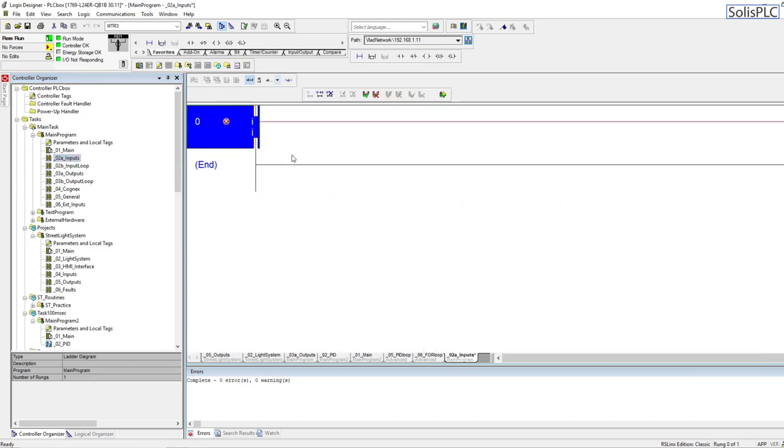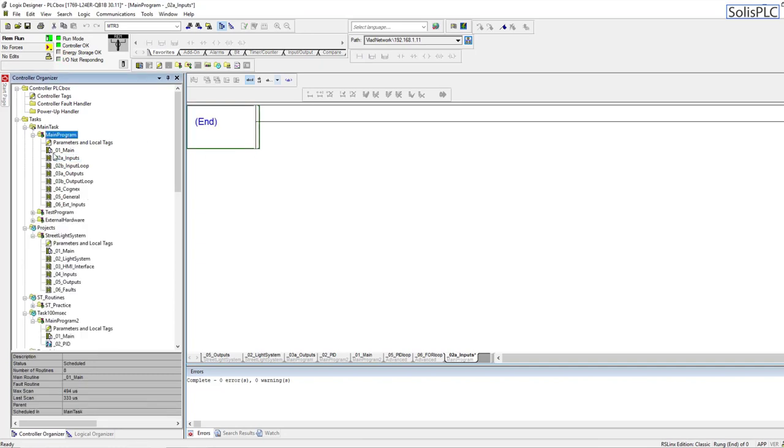So you're going to have an input which comes in, then it's going to scale to a value that we can understand easily, and then it's going to be used in the program. For example, a certain pressure level or a certain distance is going to come in as a value from 0 to 16,000, and then you'd scale that to PSI or bar, or for example meters, inches, or feet, so that you can easily program the conditions, and then based on those conditions, you can easily program certain other features. That being said, how do we do the scaling?